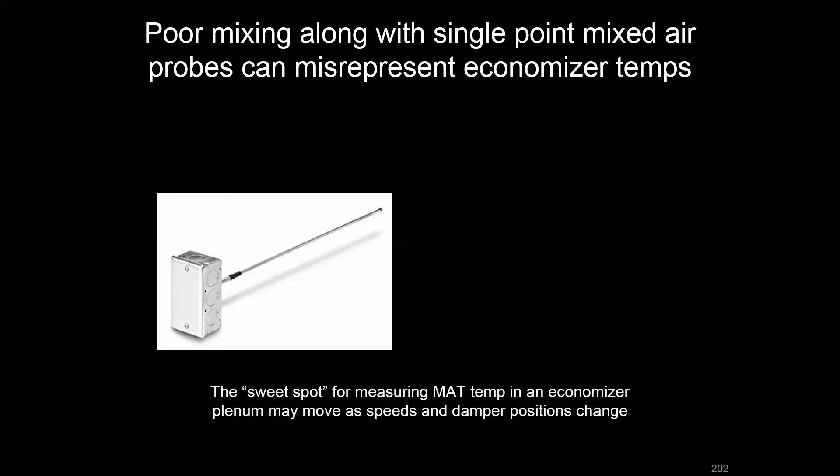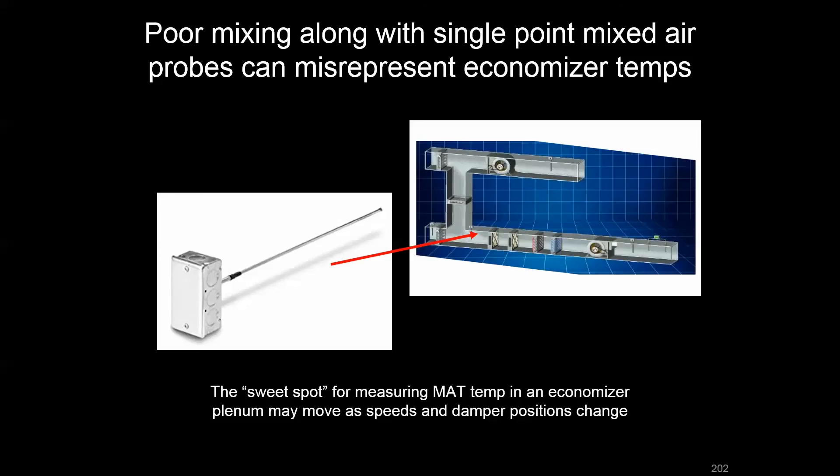Using a point or probe sensor instead of an averaging sensor creates additional problems. You lose the ability to see average mixed air temperature, and even if you find a sweet spot in the plenum, that sweet spot may shift at different damper positions and fan speeds.